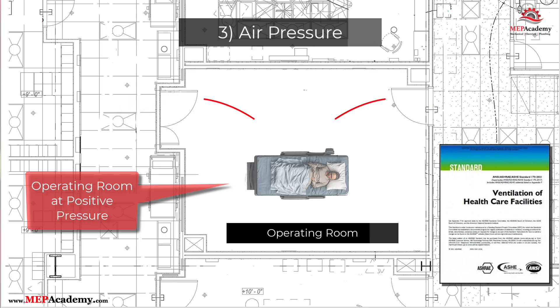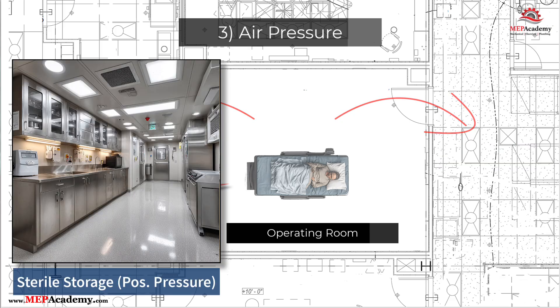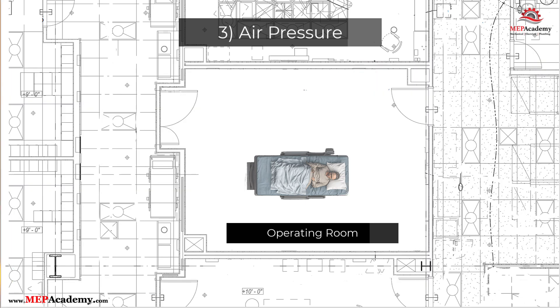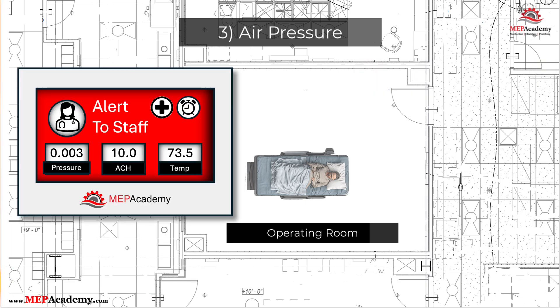The operating room is positively pressurized compared to corridors and adjacent support spaces. Sterile storage rooms are also positively pressurized to protect clean supplies. In contrast, soiled utility rooms or decontamination areas are kept at negative pressure to contain contaminants. These pressure differentials are actively monitored using sensors and pressure gauges. If pressure drops below the required threshold, alarms are triggered to alert staff. This directional airflow ensures that airborne particles from dirtier areas cannot flow into sterile spaces — critical for infection control.